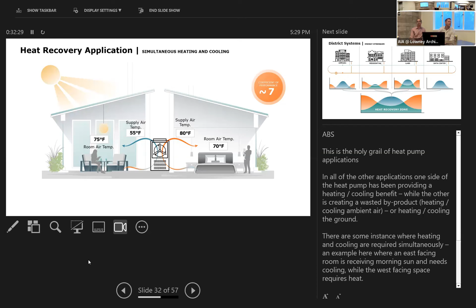So in this case, the heat pump is drawing heat out of the room on the left that needs cooling. It amplifies the temperature of that heat and pushes it into the room on the right and heats it. And because both sides of the heat pump are now providing a benefit, you'll get a COP of 7, sometimes almost 8. So this is like the most efficient way that you can use a heat pump.